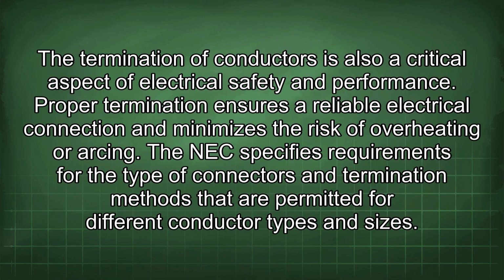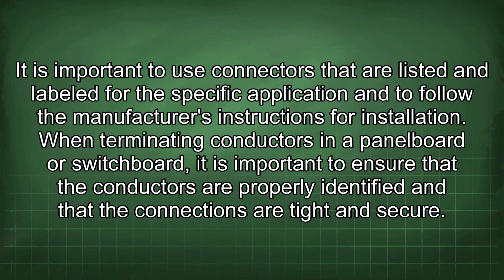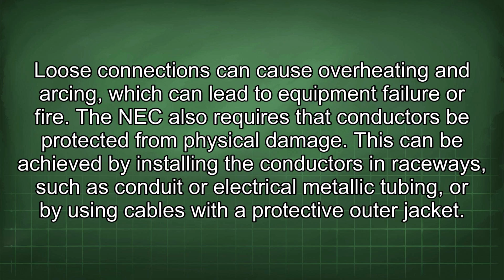The termination of conductors is also a critical aspect of electrical safety and performance. Proper termination ensures a reliable electrical connection and minimizes the risk of overheating or arcing. The NEC specifies requirements for the type of connectors and termination methods that are permitted for different conductor types and sizes. It is important to use connectors that are listed and labeled for the specific application and to follow the manufacturer's instructions for installation. When terminating conductors in a panel board or switchboard, it is important to ensure that the conductors are properly identified and that the connections are tight and secure. Loose connections can cause overheating and arcing, which can lead to equipment failure or fire.